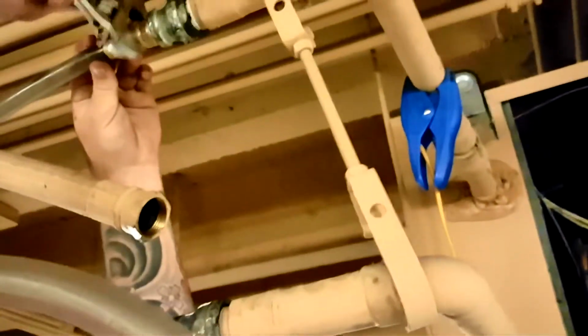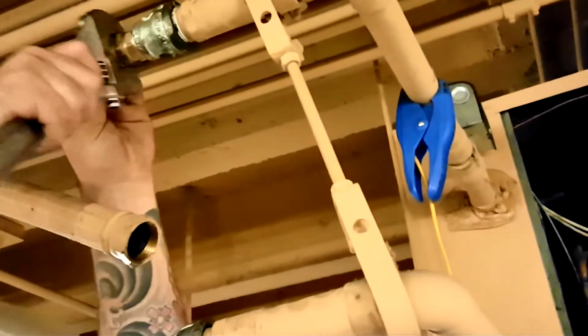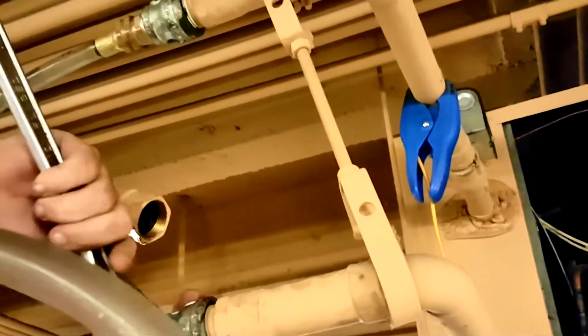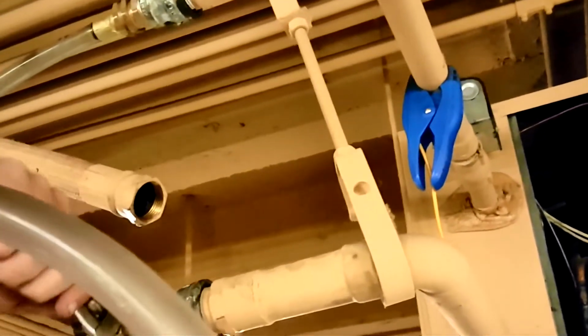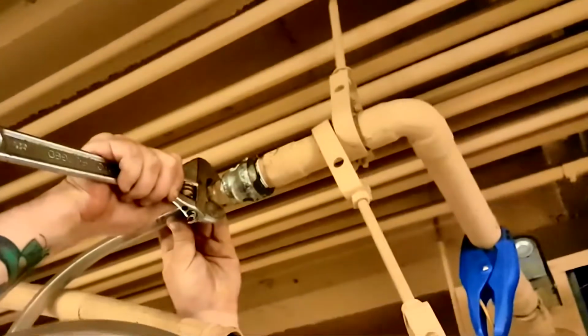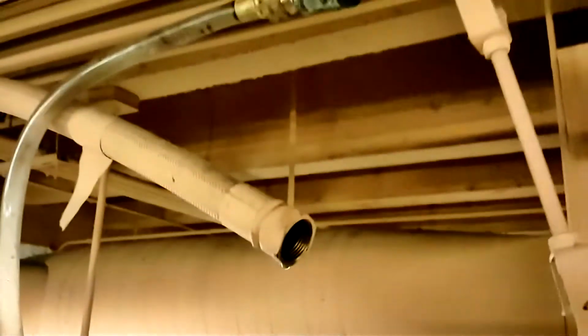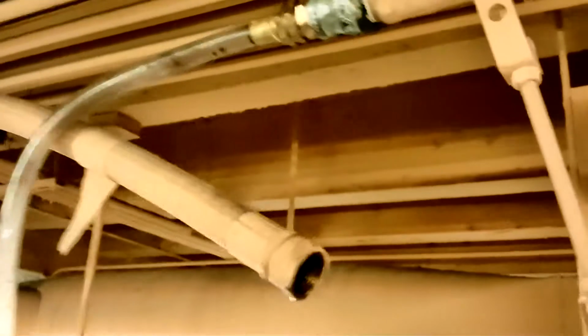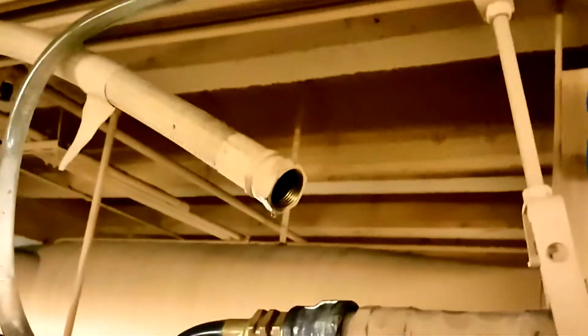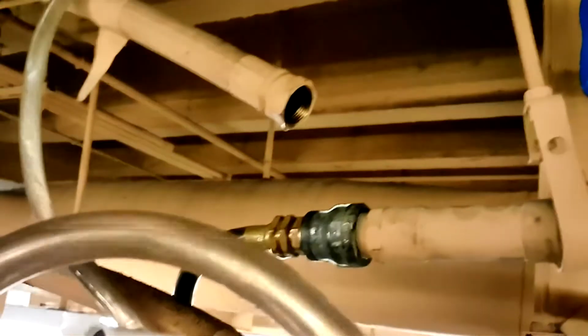So he's going to make sure that the connections are nice and tight for both the return and the supply water. Once everything's connected, make sure everything's nice and tight, we're going to go ahead and turn the pump on. Okay, so now we're going to be turning the pump on to be introducing the chemical into the system. So as you can see, the chemical's going in, and it's going to start coming out from the top once the chemical starts flowing through.